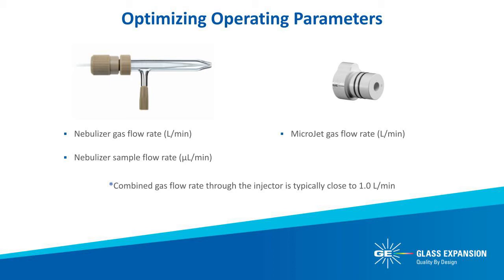We will review the optimization of nebulizer gas flow rate, sample flow rate, and microjet gas flow rate. These operating parameters affect the transport efficiency of the aerosol and, with respect to single cell analysis, the integrity of the single cells remaining intact during nebulization. The combined gas flow rate of the nebulizer and microjet typically is approximately equal to one liter per minute argon in order to create a robust plasma.